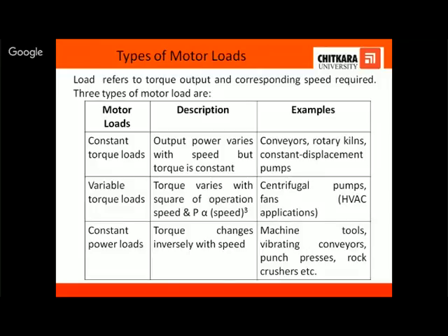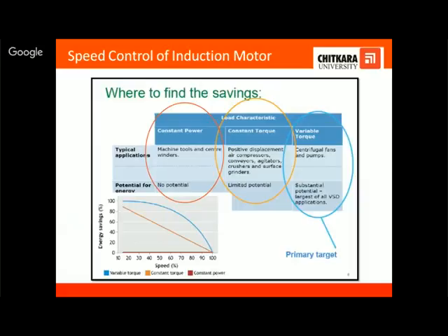When we talk about the variable torque loads, the torque varies with the square of the operating speed and the power varies as the cube of the speed. So all the centrifugal pumps, fans, and HVAC applications have variable torque loads. And this is the area where you get the maximum energy saving. Then we have constant power loads, where the torque changes inversely with the speed. The examples are machine tools, vibrating conveyors, punch presses, rock crushers, etc.